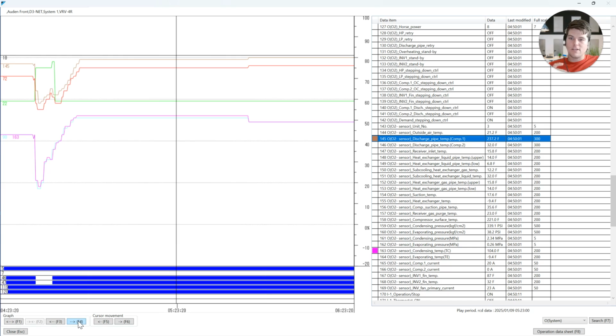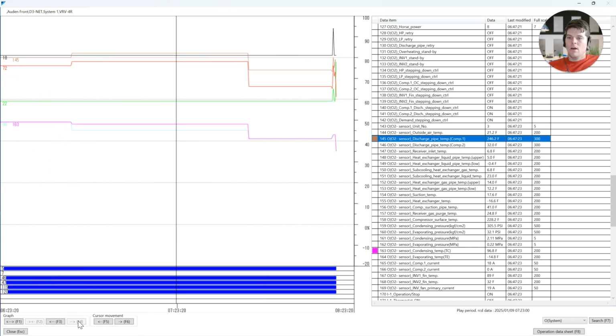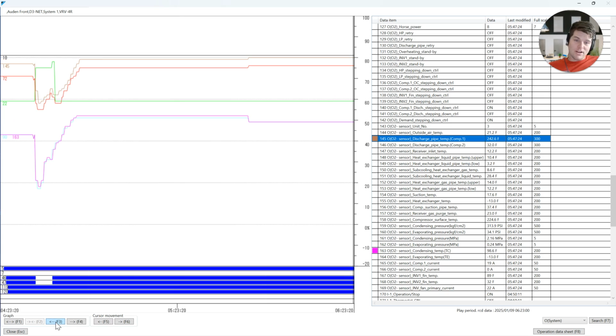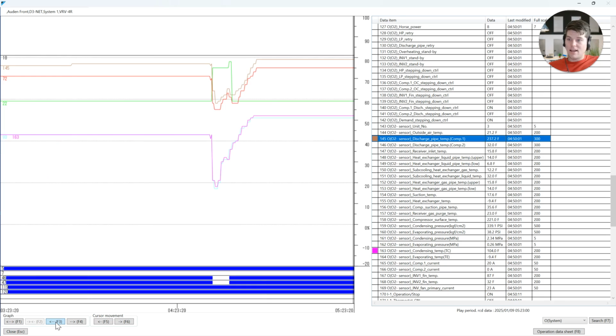Again, we've got another defrost cycle there, only in 1 coil, not both. But I mean, look at it, guys. This discharge temperature, 246 now. Man, crazy, crazy, crazy high. This is not good. High discharge superheat is really not good. And I say high, 151 degrees. I even clocked it at 168 at some point.